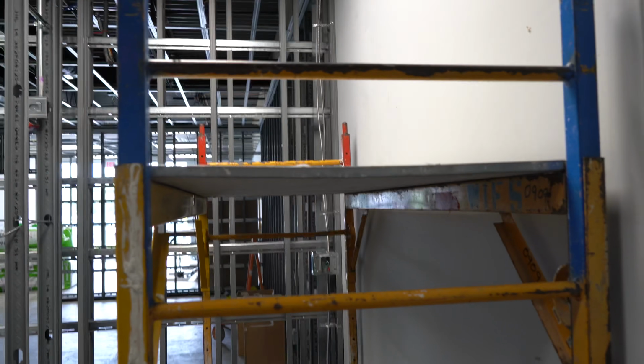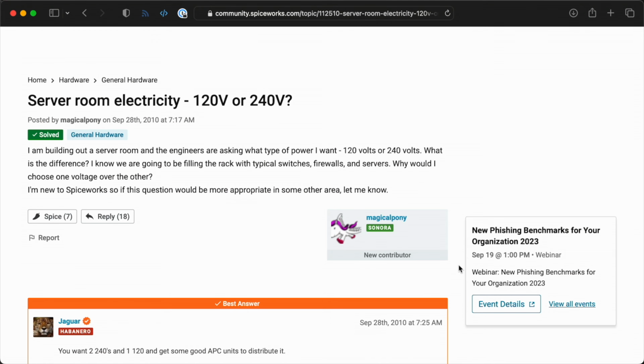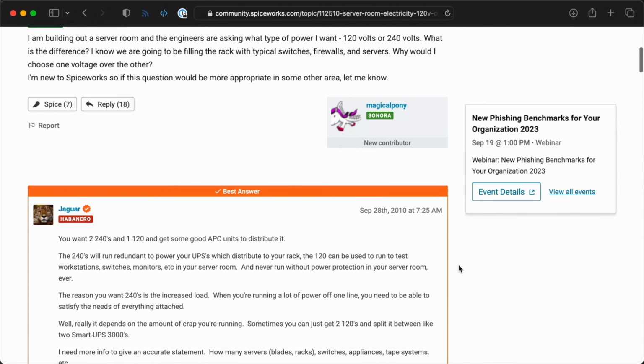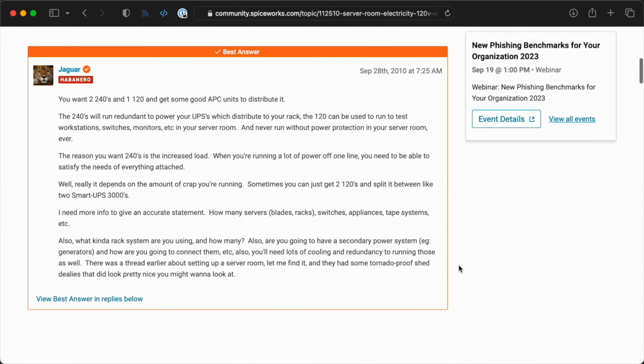I also had the electricians put in 2 separate independent ground circuits for the server room, which isn't strictly necessary, but I should explain why. First, that'll give me 40 amps at 120 volts. Some people would go to 240 volts in the server room, but not all the gear I'll be using is rated for that voltage. Higher voltage is more efficient, usually, and you can get more power in the same cabling.